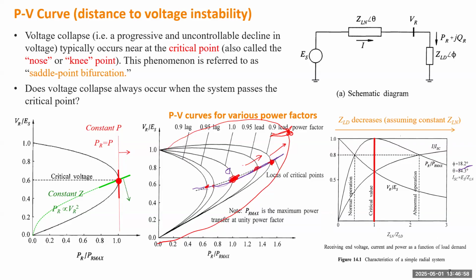Okay. So for such an area, voltage collapse can happen more easily, even before the voltage declines. It can happen near normal voltage. So we have to have this curve and identify the critical point, then measure the distance from your current operating condition to that point. That really tells the margin. It's not safe just to compare with a threshold. Maybe let's use 0.8 as a threshold. If my current voltage is 0.9, I have a 0.1 margin, but that's not safe because the critical voltage can be even higher than 0.9. So always maintaining high voltages cannot prevent voltage instability.